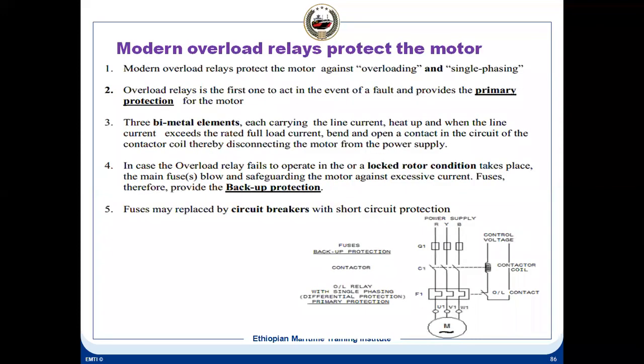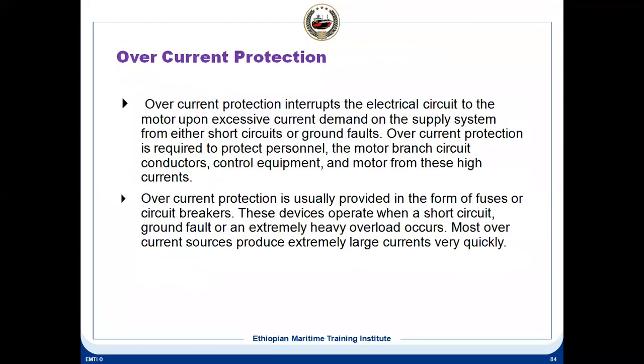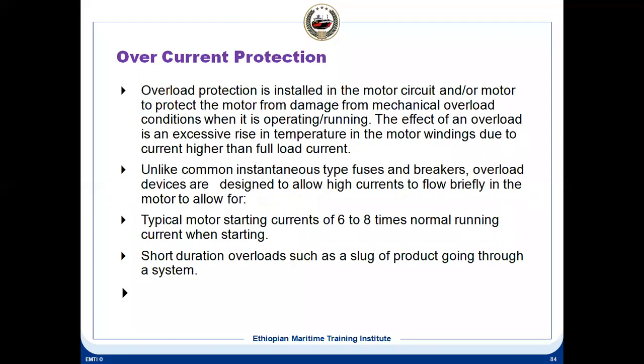Let's come to overcurrent protection and voltage protection. Overcurrent protection basically interrupts the electrical circuit to the motor in case of excessive current demand on the supply system from either a short circuit or a ground fault. Overcurrent protection is required to protect personnel, motor, conductors, and control equipment from these high currents. Overcurrent protection is usually provided in the form of fuses or circuit breakers. These devices operate when a short circuit, ground fault, or extremely heavy load occurs. Most overcurrent sources produce extremely large currents. Overload protection is installed in the motor circuit.